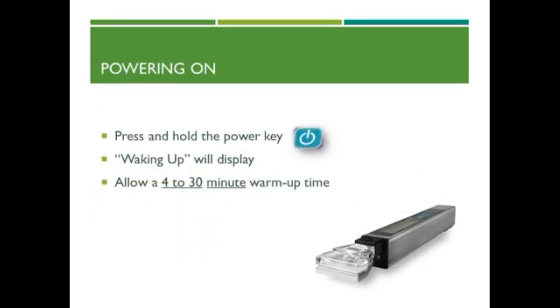When powering on the instrument, press and hold the power key for 2 to 5 seconds. You will see the words "Waking Up" displayed on screen. Allow at least 4 minutes for the unit to properly warm up before taking measurements, or up to 30 minutes for proper acclimation to the testing environment. Warm-up time will be longer if the CI-340 internal temperature is cold or if the CO2 analyzer has aged. There's a fail-safe that will not allow you to begin a measurement until the CI-340 is sufficiently warmed up.